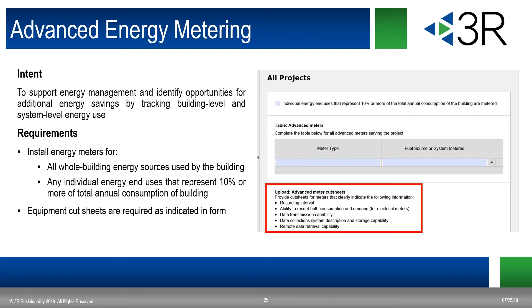In order for the submeters to comply, they must have the characteristics as shown here. They've got to be permanently installed, record at intervals of 1 hour or less, and transmit data to a remote location. Electric meters have to record both consumption and demand. Your data collection system must use a local area network, building automation system, wireless network, or something comparable. The system must be capable of storing all data for at least 36 months. Your data must be remotely accessible, and the meters must be capable of reporting hourly, daily, monthly, and annual energy use.